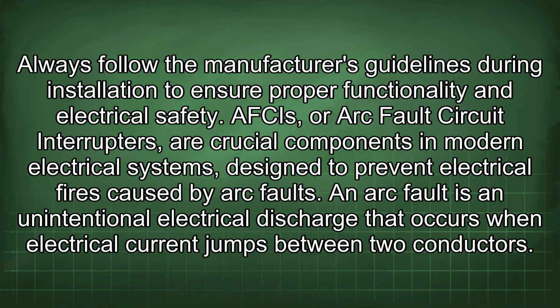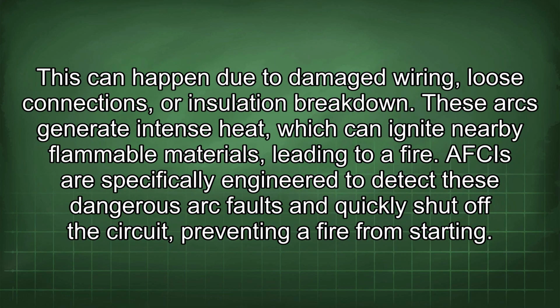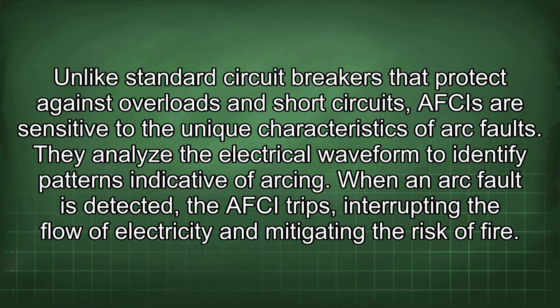AFCIs, or arc fault circuit interrupters, are crucial components in modern electrical systems designed to prevent electrical fires caused by arc faults. An arc fault is an unintentional electrical discharge that occurs when electrical current jumps between two conductors. This can happen due to damaged wiring, loose connections, or insulation breakdown. These arcs generate intense heat, which can ignite nearby flammable materials, leading to a fire. AFCIs are specifically engineered to detect these dangerous arc faults and quickly shut off the circuit, preventing a fire from starting. Unlike standard circuit breakers that protect against overloads and short circuits, AFCIs are sensitive to the unique characteristics of arc faults. They analyze the electrical waveform to identify patterns indicative of arcing. When an arc fault is detected, the AFCI trips, interrupting the flow of electricity and mitigating the risk of fire.